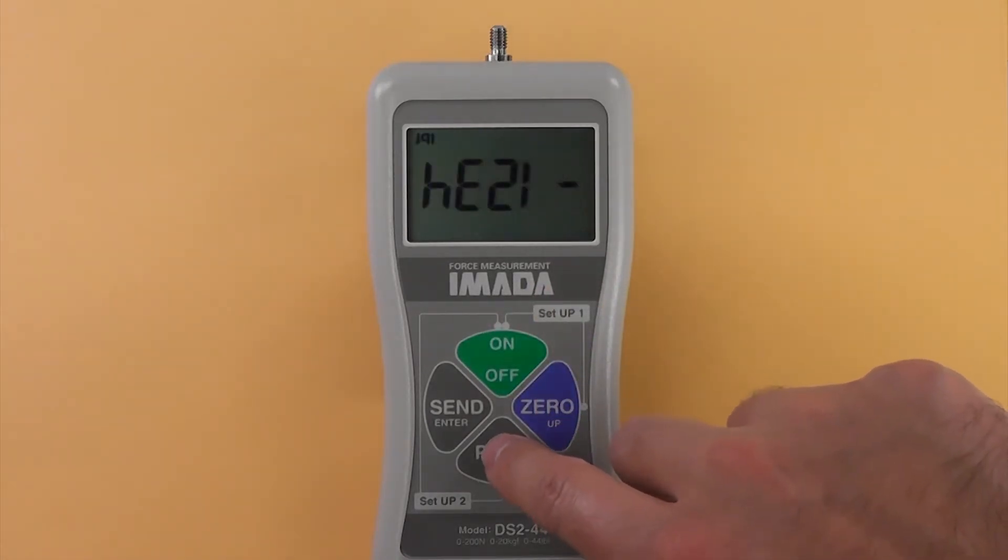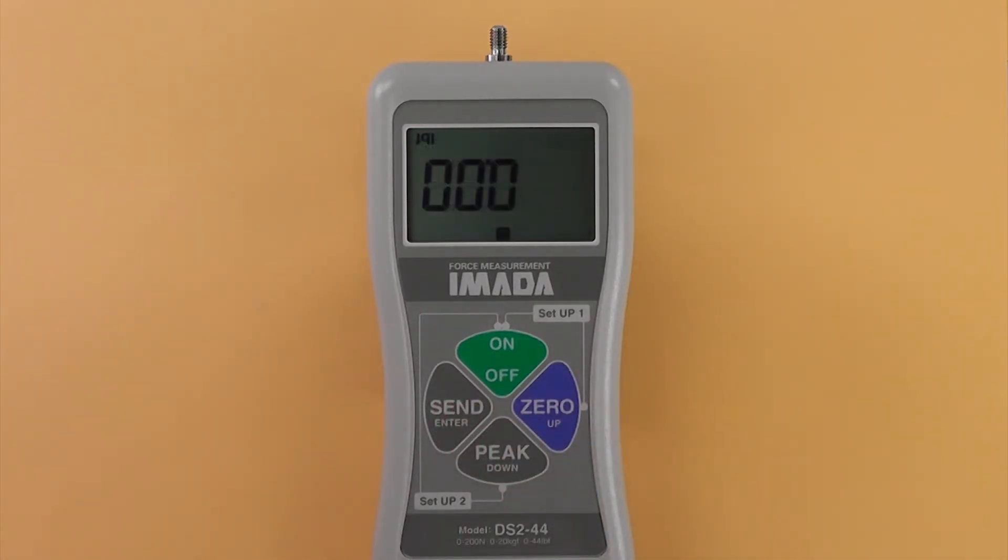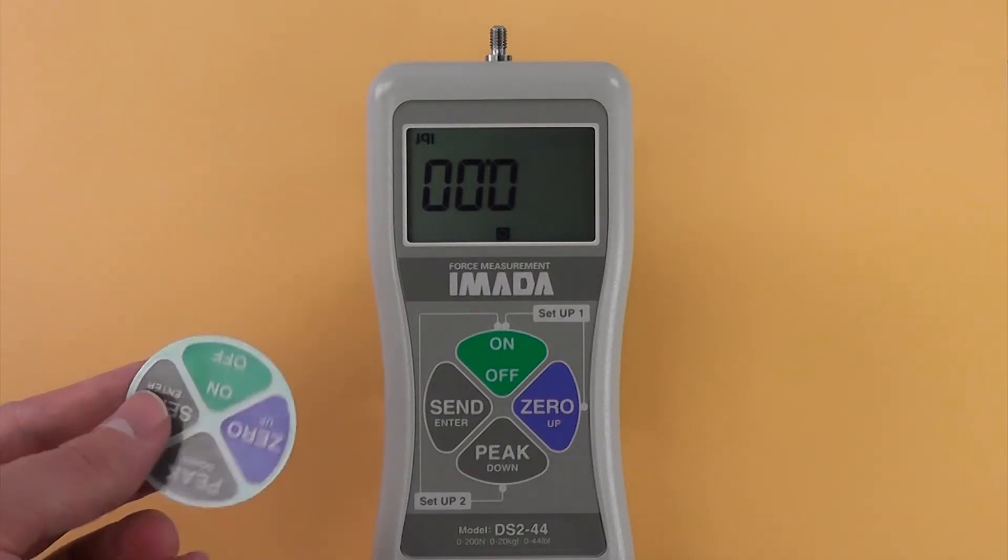Press PEAK to cycle between standard and reverse display. Press SEND to select. For easier readability, the reverse display sticker can be attached to a gauge mounted to a test stand.